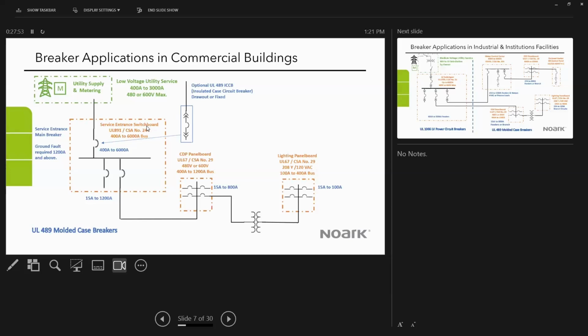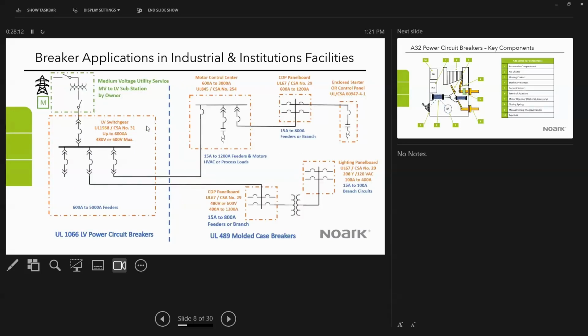And again, it feeds successive layers of distribution through to a CDP type panel board, and ultimately through a transformer down to the lighting and appliance panel board that would be giving you that branch circuit protection. And moving on to even larger facilities, the major difference here is scale in both voltage and ampacity. Many utilities will serve a large industrial or institutional facility with a medium voltage feed. In that case, the owner of the building would be required to have a medium voltage to low voltage substation to bring the voltage down to the usable level of 480 volts or 600 volts in Canada.